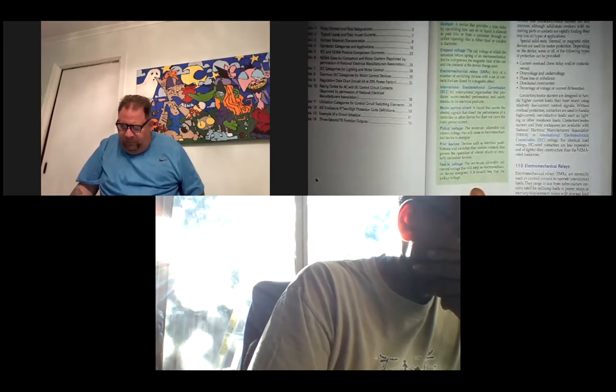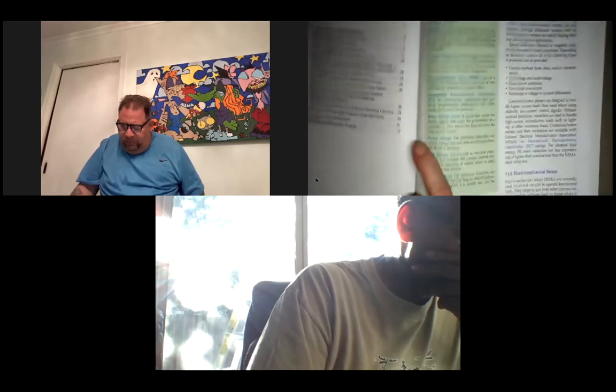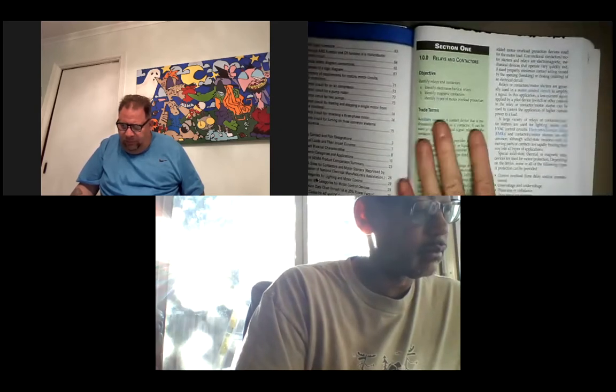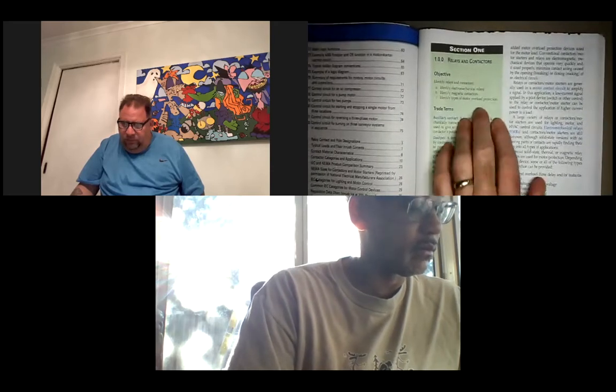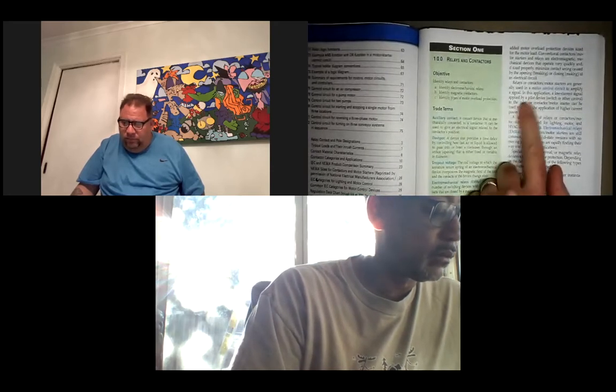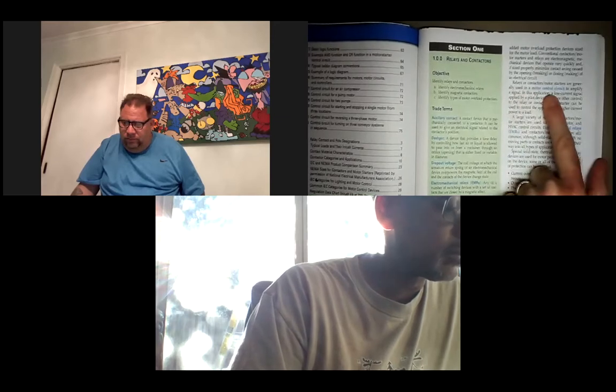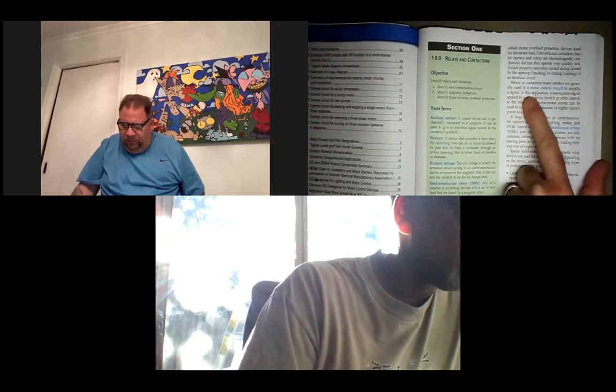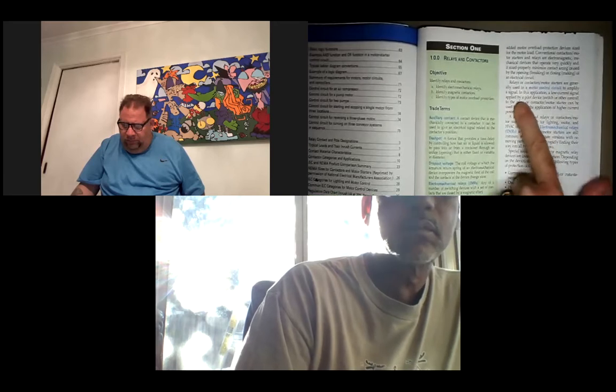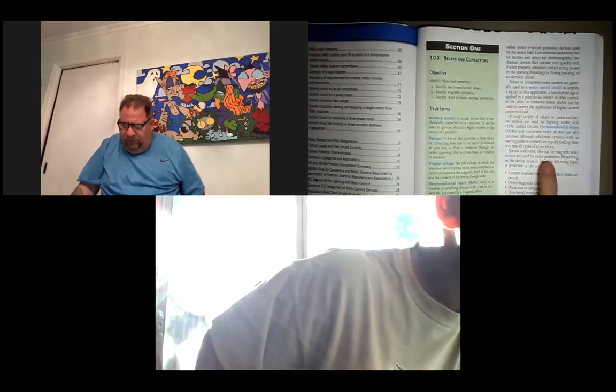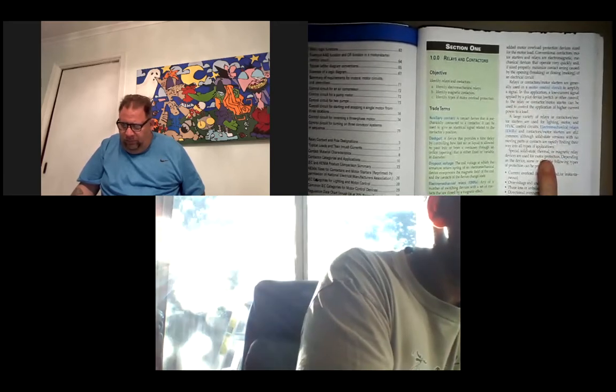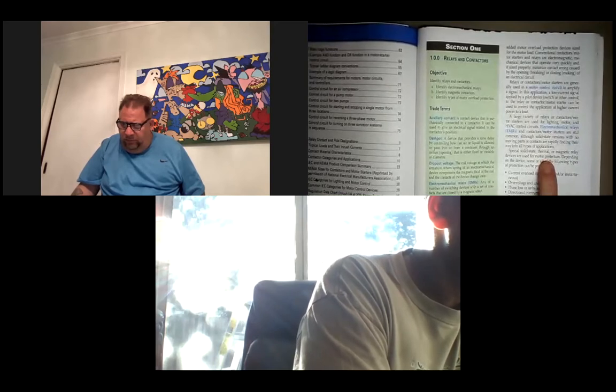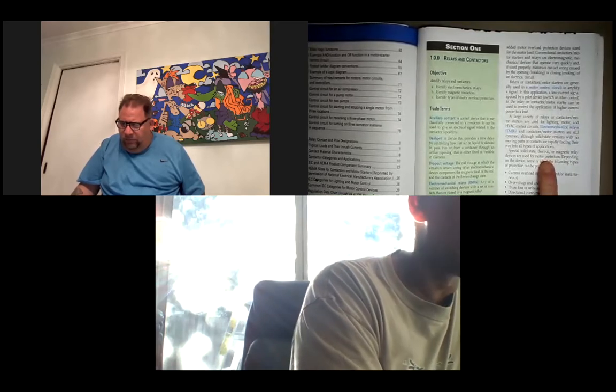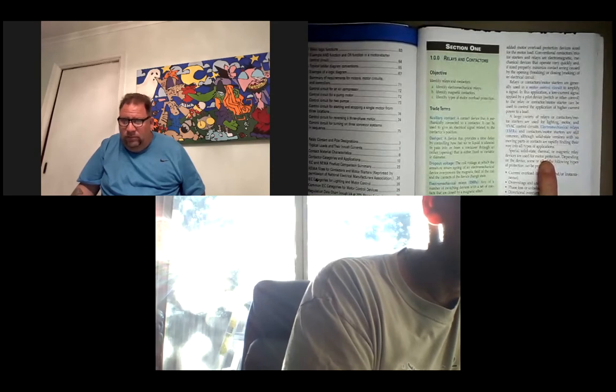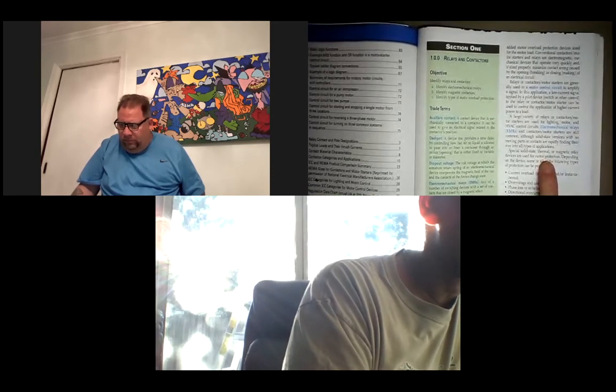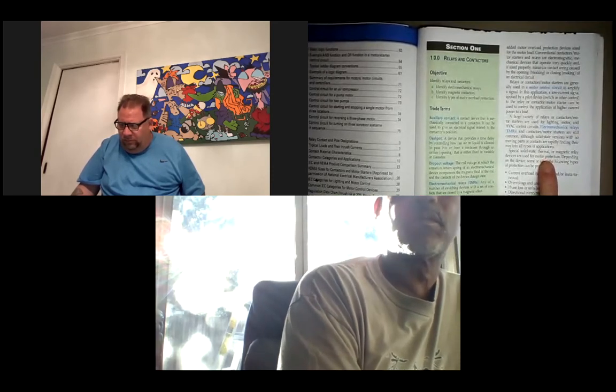All right. I don't have any highlights on page 1. That's always a bad thing because there's usually a lot of good information. As relays or contactors, motor starters are generally used in a motor control circuit to amplify a signal. So they might use 120 volts in order to operate the contactor, but the motor can run on 480 volts. It's safer to use 120 volts as the control voltage rather than 480. That's why they do it.